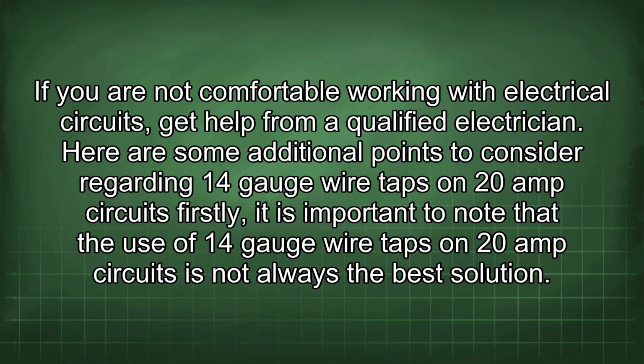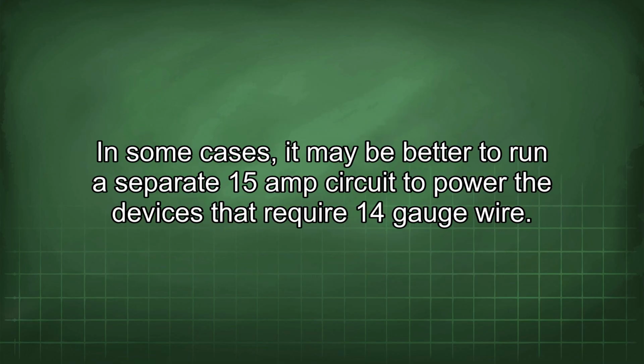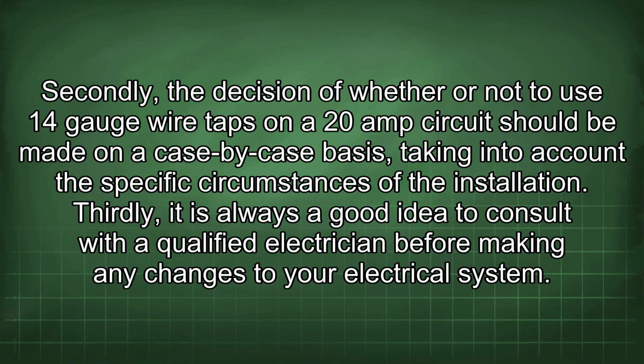Here are some additional points to consider regarding 14-gauge wire taps on 20-amp circuits. Firstly, it is important to note that the use of 14-gauge wire taps on 20-amp circuits is not always the best solution. In some cases, it may be better to run a separate 15-amp circuit to power the devices that require 14-gauge wire. Secondly, the decision of whether or not to use 14-gauge wire taps on a 20-amp circuit should be made on a case-by-case basis, taking into account the specific circumstances of the installation. Thirdly, it is always a good idea to consult with a qualified electrician before making any changes to your electrical system.